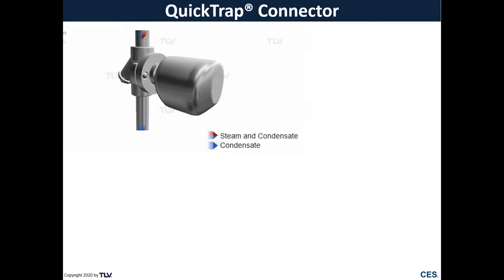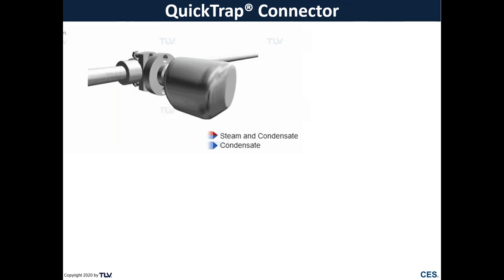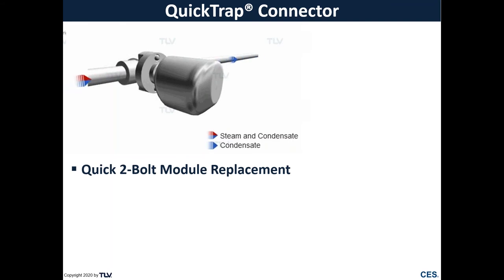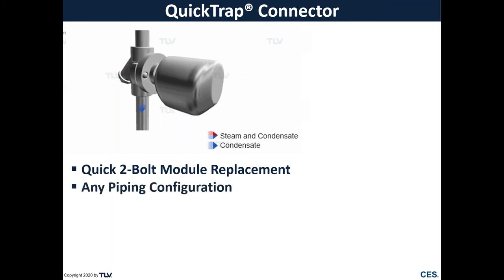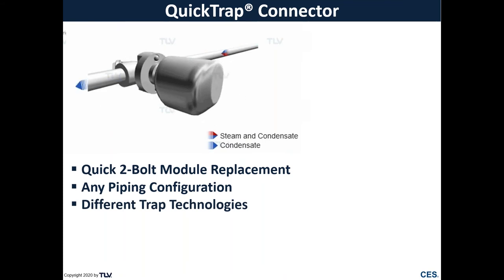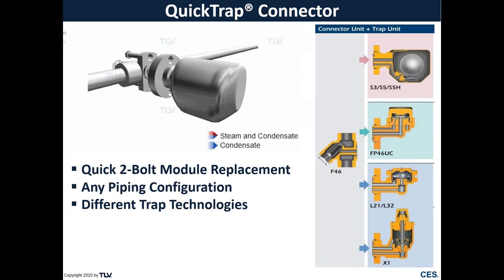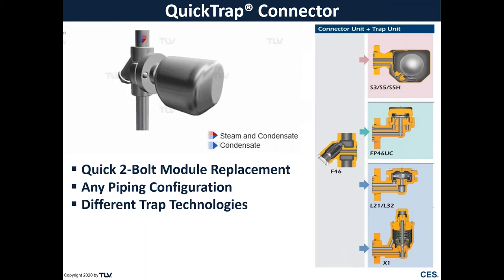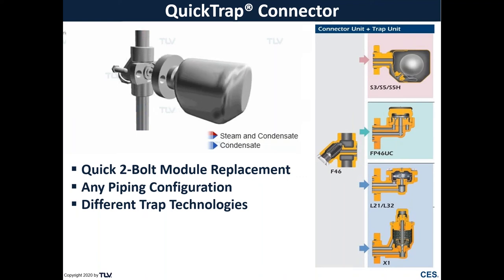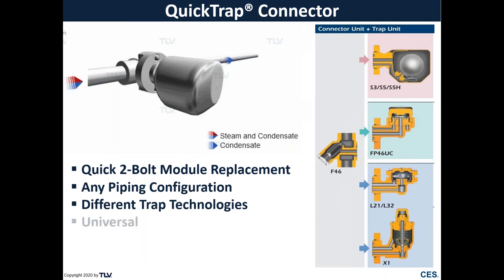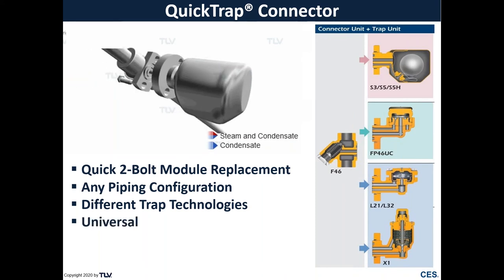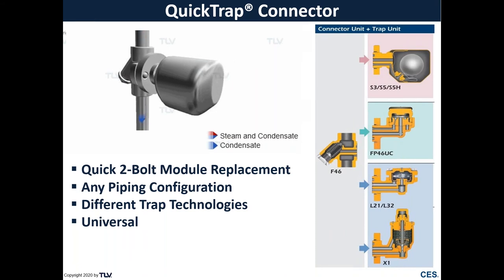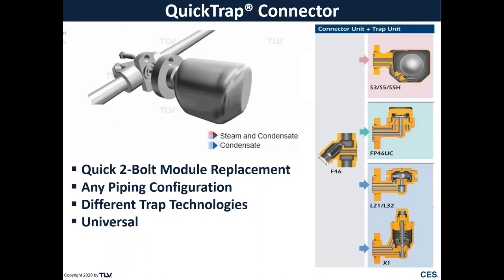Another common steam trap connection type is what we call the quick trap connector. This is a two-piece steam trap consisting of an inline connector and a steam trap module. It has a two-bolt module, which makes it easy for maintenance and replacement, and the connector can be installed in any piping configuration. And since it is a bolt-on module, there are different steam trap technologies that can be bolted onto the same connector. So here are examples of TLV's free float, along with a thermodynamic as well as thermostatic trap modules that can be attached to that same connector. And another nice thing is that it is fairly universal across most steam trap manufacturers. So many different manufacturers' connectors will fit many different manufacturers' steam trap modules.